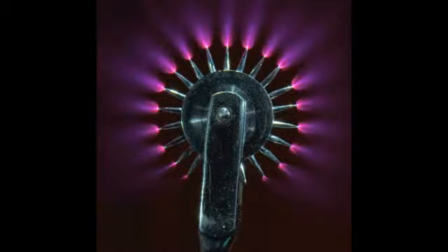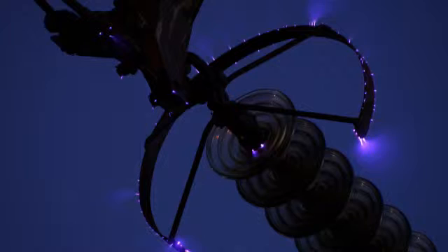It is often seen as a bluish, or other color, glow in the air adjacent to pointed metal conductors carrying high voltages, and emits light by the same property as a gas discharge lamp. In many high-voltage applications, corona is an unwanted side effect. Corona discharge from high-voltage electric power transmission lines constitutes an economically significant waste of power for utilities. In high-voltage equipment like televisions, radio transmitters, X-ray machines and particle accelerators, the current leakage caused by coronas can constitute an unwanted load on the circuit.